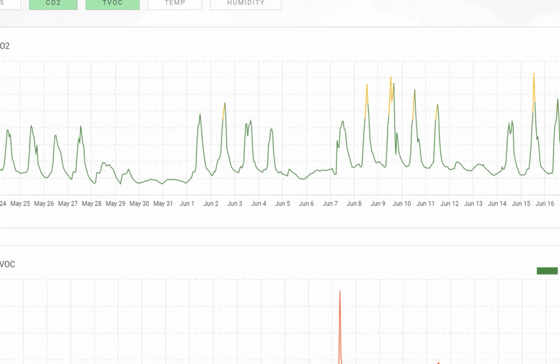What would be acceptable per ASHRAE standards is really anything up to, say, the City of Chicago ventilating code, which can be up to 1,000 parts per million. ASHRAE 62.1 says outdoor ambient plus 700, which usually gets you up to around 1,100. But clearly ASHRAE 62.1 is the minimally acceptable code for ventilation, and we're looking at something a little better than minimally acceptable here.